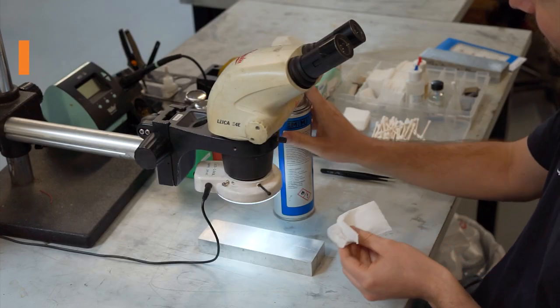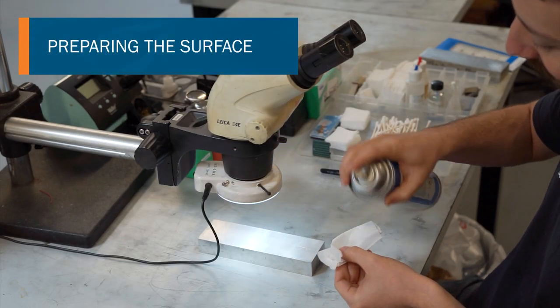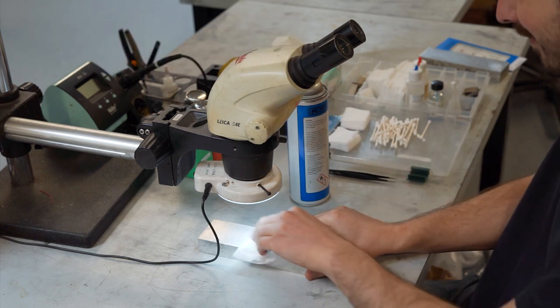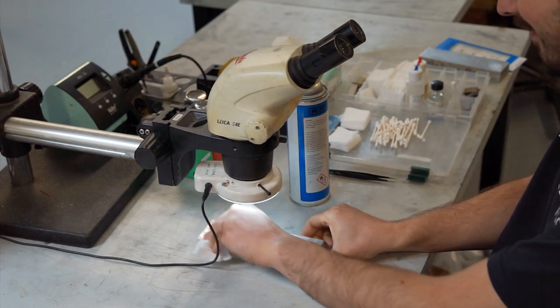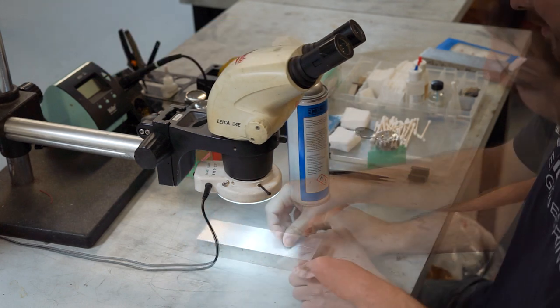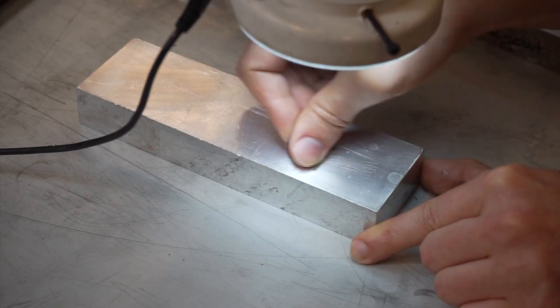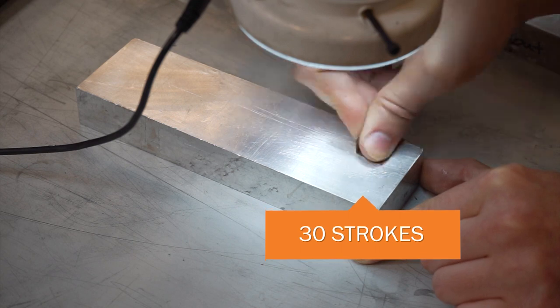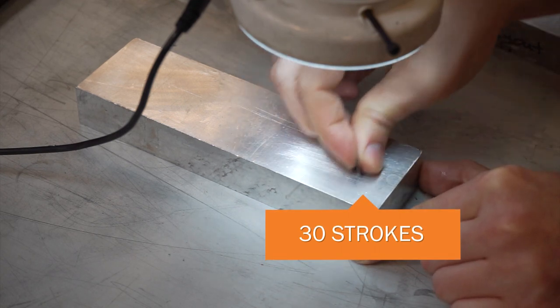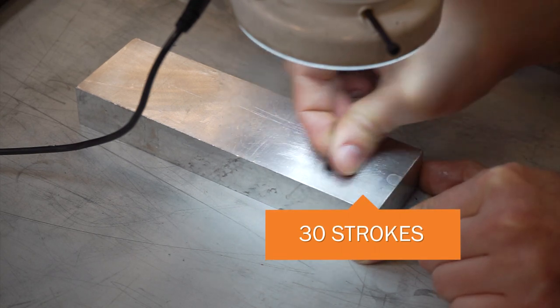The first step in applying a strain gauge is to prepare the surface. This includes solvent degreasing with a degreasing agent and isopropyl alcohol. This is followed by surface abrading over the strain gauge application area. 30 strokes should be done in the vertical, horizontal and diagonal directions.